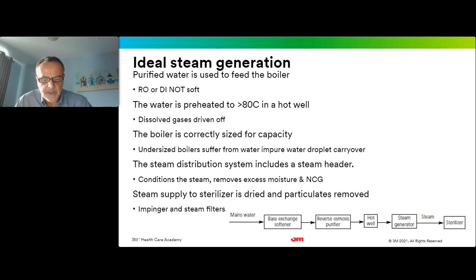So let's consider what the ideal method of generating steam is. First of all, attention should be paid to the use of some form of purified water in the boiler feed system rather than softened water. Ideally, the water should be preheated to 80 degrees C in a hot well before it is fed into the boiler. And this will drive off any dissolved gases, as we've seen with those jars of tap water. If you heat the water up, the gases will be driven off.